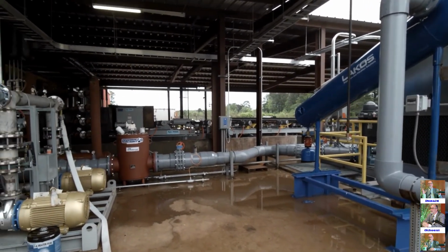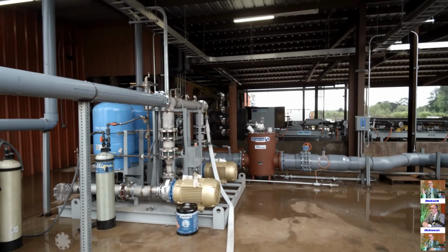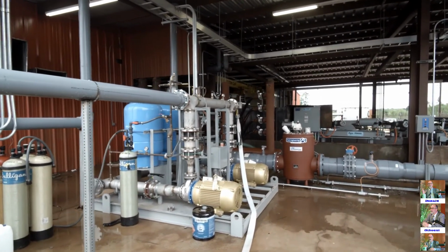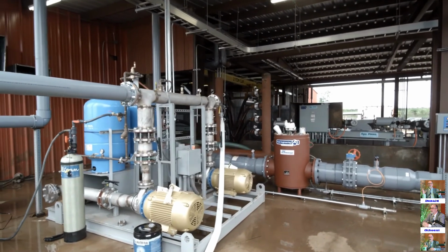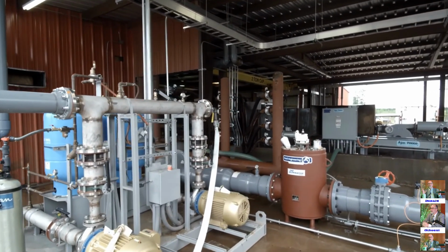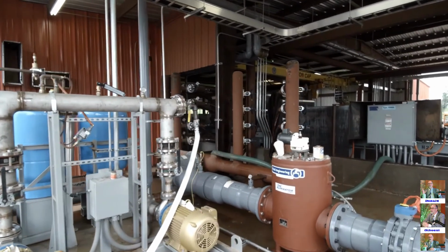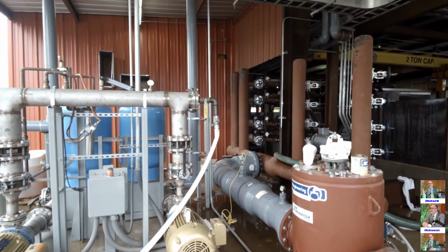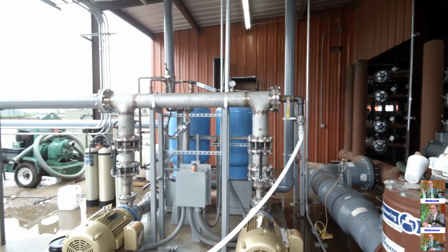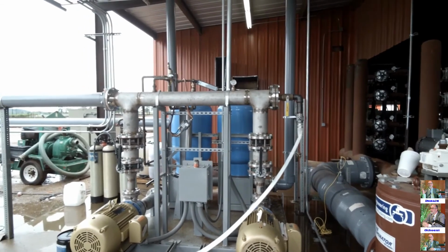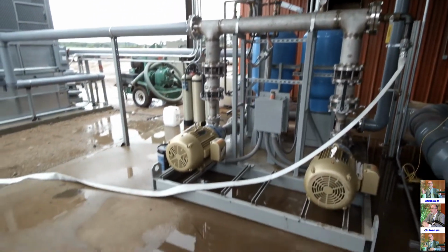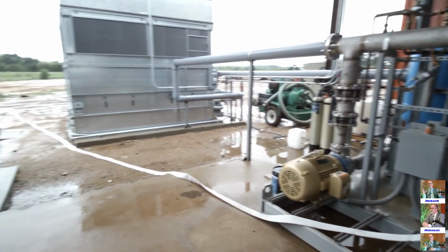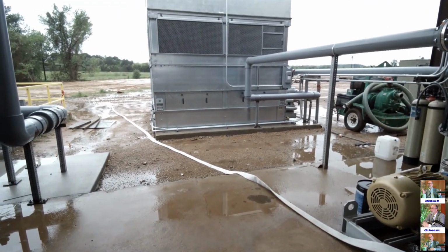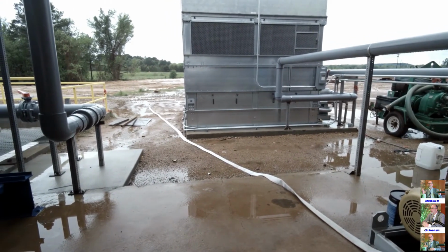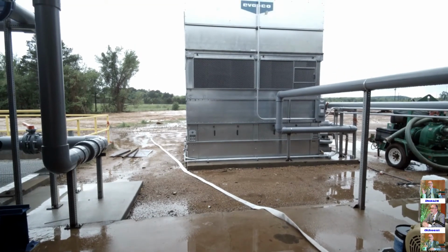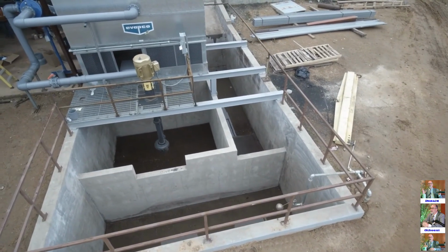And then the two pumps you saw to the right there pump it back through this fine particulate matter filter right in front of you, the brown filter, right before the quench headers, which you can see are vertical here with individual flow control valves to control the pressure, so we can equalize out that quench all the way around the circumference of the barrels and the rings, and that compensates for any 90s in the plumbing or longer runs. That's how precise you want to have that quench. This is the water system, a dual pump for the closed pressurized power supplies, the rolls, the coils. One goes out, the other one kicks in automatically.